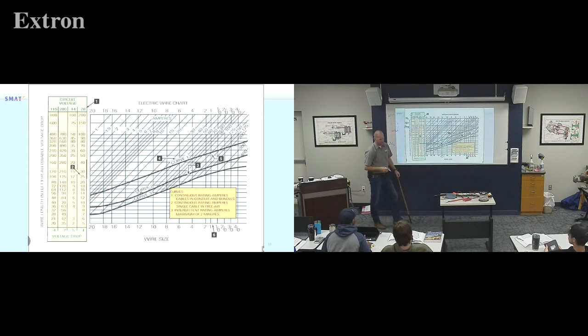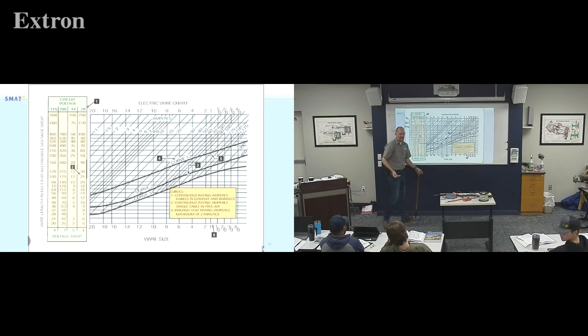So it wouldn't work, so they had you do it in 2 steps. They'd say 12 gauge, okay, well go back up to your 30 and make sure it doesn't drop below. Whoops, we dropped below, we crossed that line. So what they would do is have you stop at the line and go straight down. So instead of 12, you'd end up picking a 10. That's how that chart works.